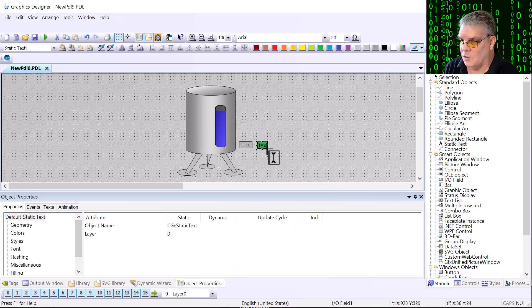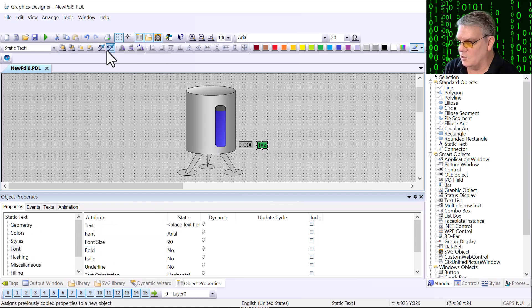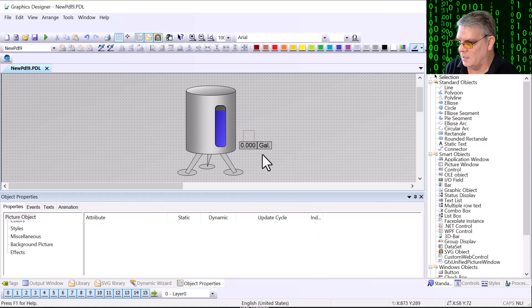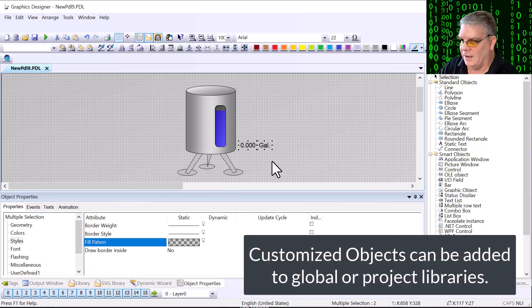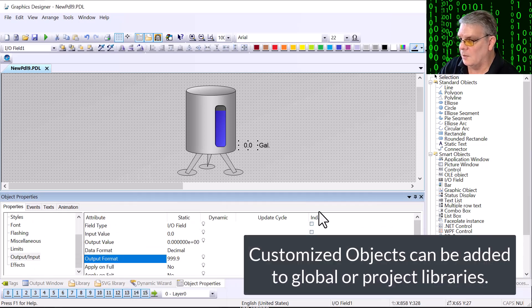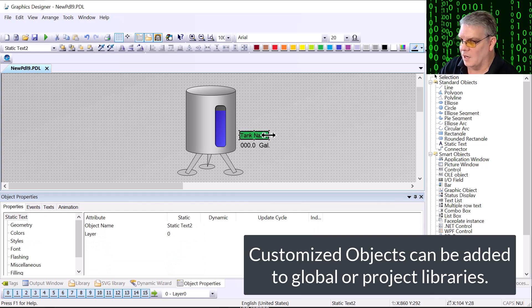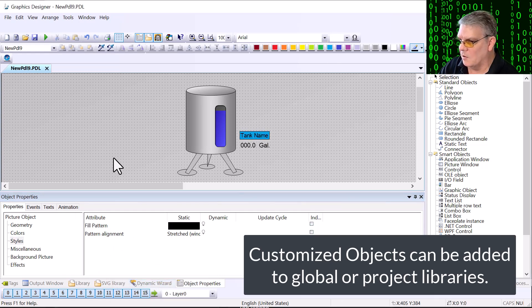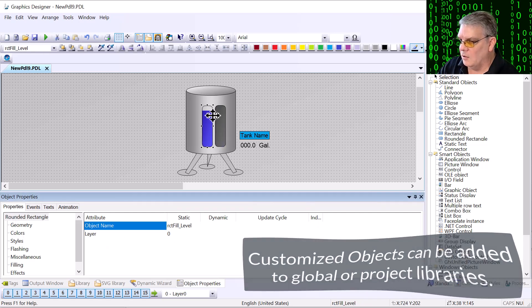Customized objects are also easier and more intuitive to integrate into your WinCC project since you can create your own set of custom properties and events. While customized objects are not global in nature, you can drag them into your global or project library and use them when needed. You can even transfer them to other WinCC projects simply by copying over PDL files to the new project or transferring the entire project library file.